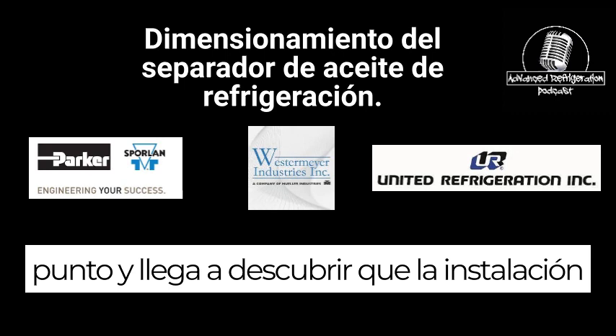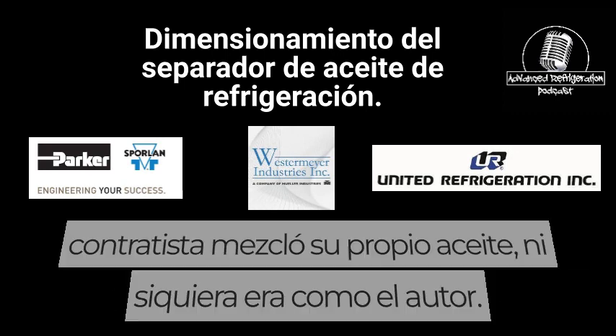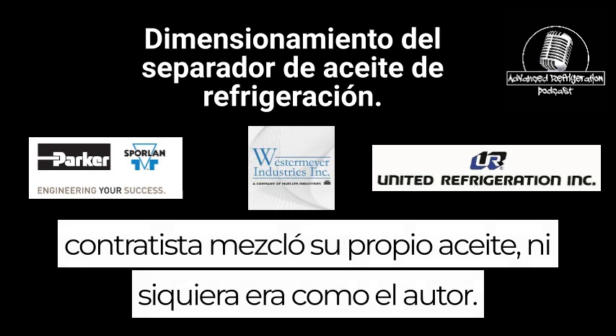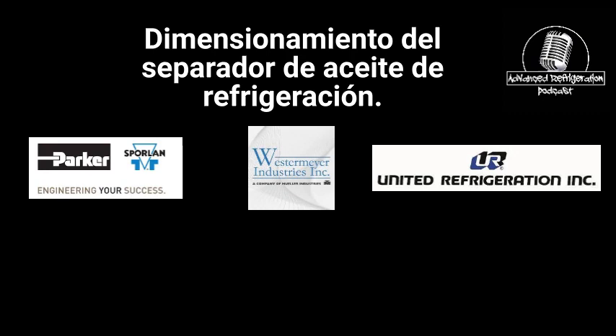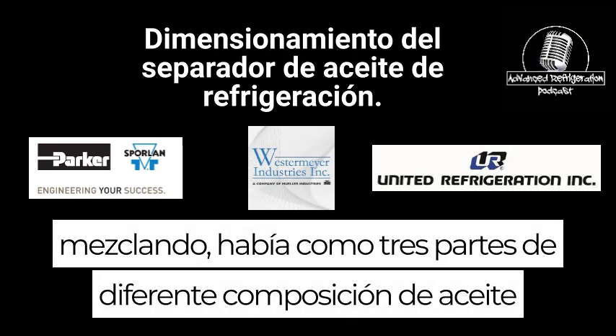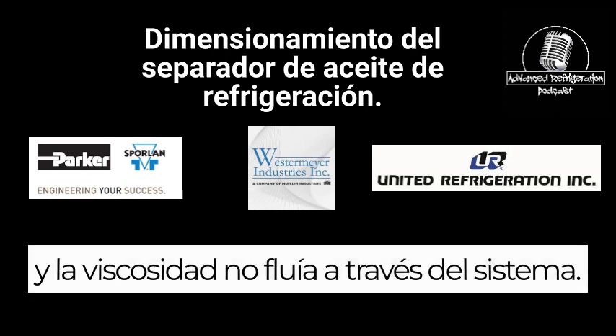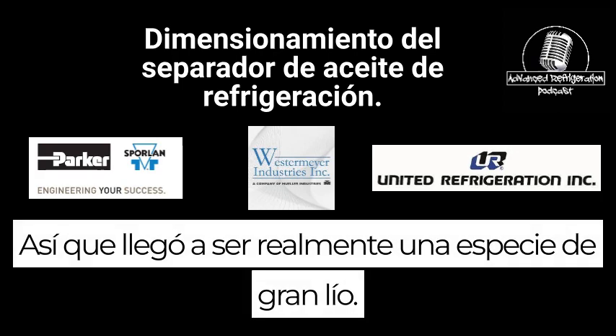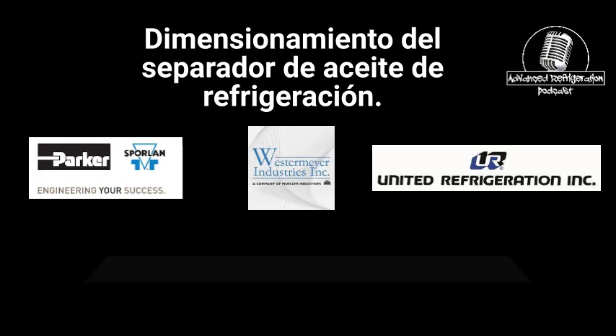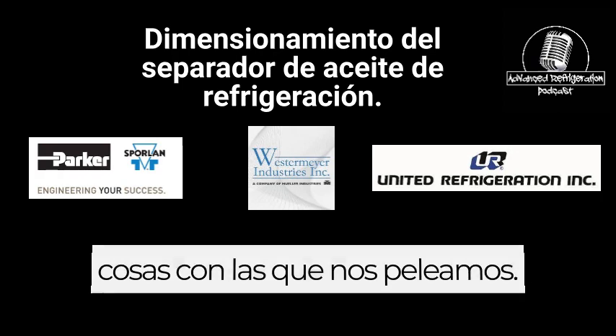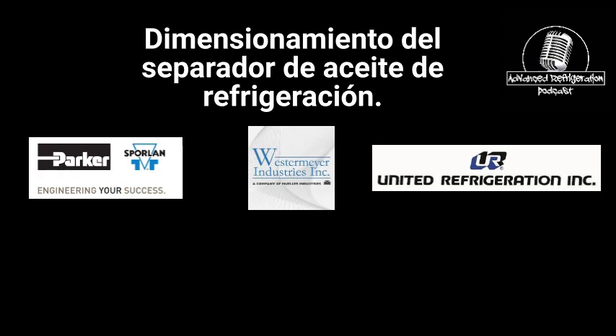It came to find out that the installing contractor had mixed his own oil. They finally did an oil test and found they were mixing about three different oil compositions, and the viscosity wasn't flowing through the system. It got to be a really big mess, but we finally got through that one. So you'd be surprised at the stuff we get wrangled up with. It's amazing. Wow.